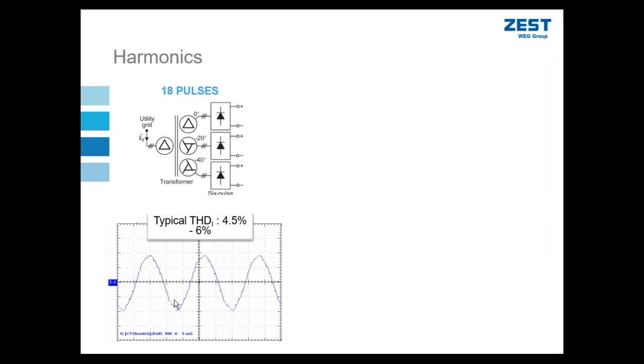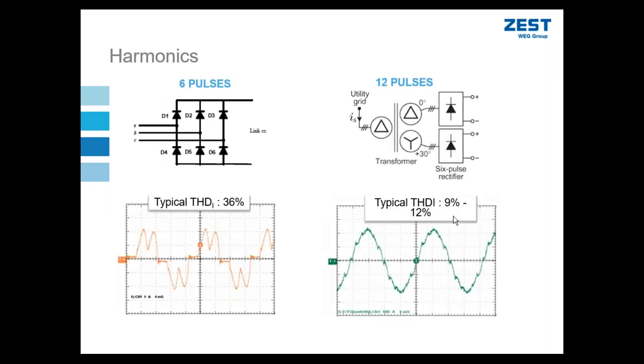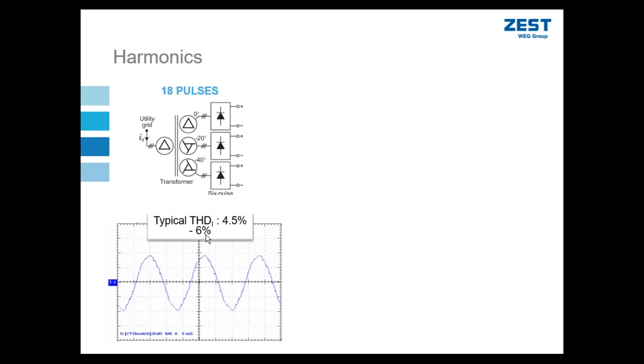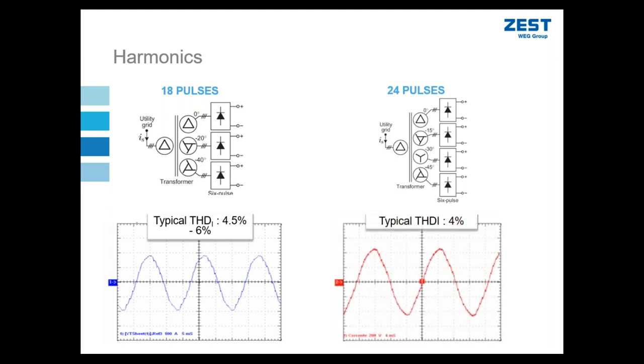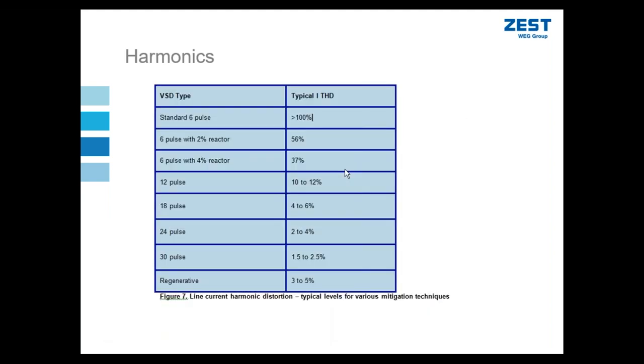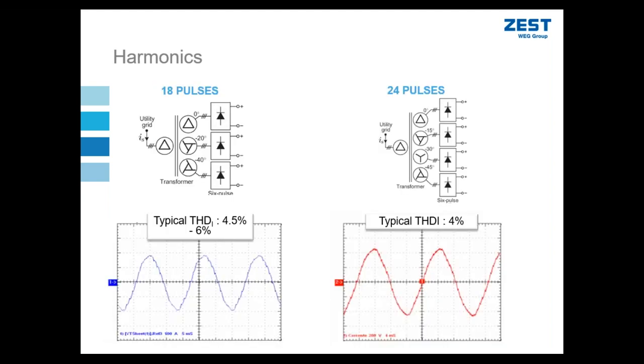However, I'm benefiting from an improved sinusoidal waveform, but I'm adding complexity to my device. In order to improve from a THD of between 9 and 12, let's go in the middle, let's say to improve on a THDI of 11%, let's say 10%, to bring it down to 5%, I need to add at least one additional secondary winding into my transformer and one additional diode rectifier. Then I look at a 24 pulse scenario. Here I've got to add at least one more secondary and one more bridge rectifier. This would bring my THDI down to 4%. What we are noticing is, as we are adding complexity and increasing the number of pulses, I'm getting a diminishing return curve on my THDI performance.